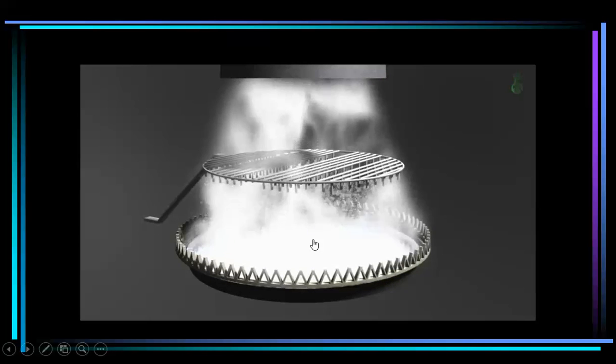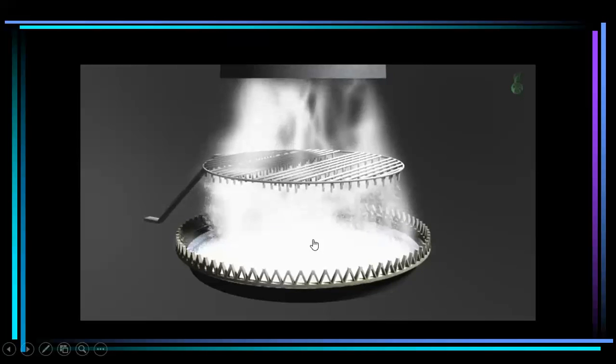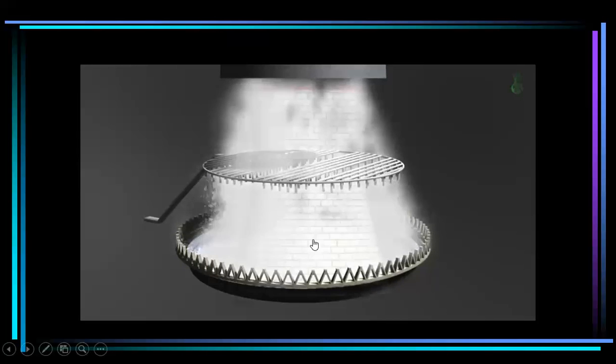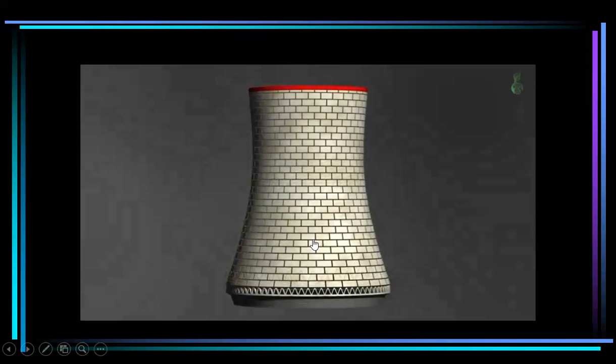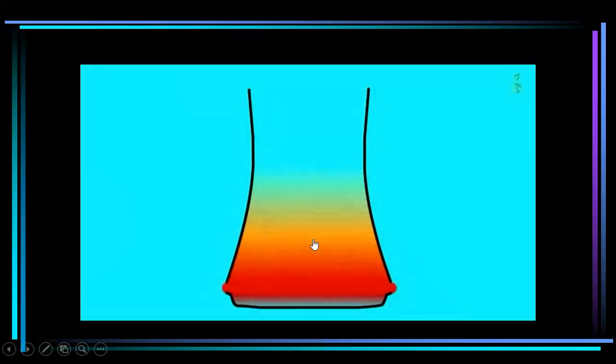Natural draft wet cooling towers function according to the simple principle of the stack effect, also known as natural circulation. Since warm air is less dense than cold air, warm air rises due to buoyancy and escapes out, so warm air rises and has to be replaced by cool air from outside rushing in.